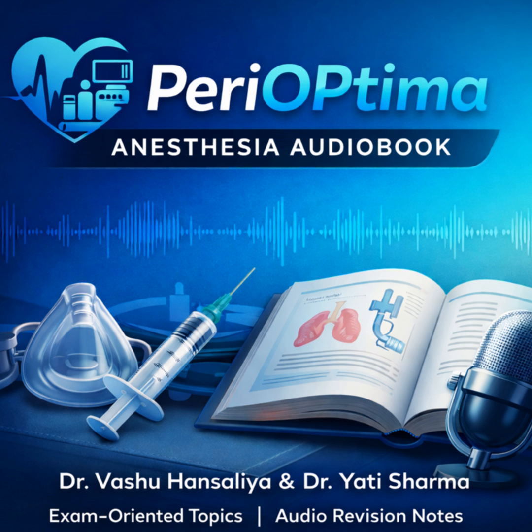Precisely. There's another benefit, too. When steam condenses, it shrinks in volume by a factor of over 1,000. This creates a local suction effect, a partial vacuum, that actively pulls more fresh steam into the pack. That's why steam penetration into wrapped bundles is so incredibly effective. That's a fantastic explanation. It's not just hot air, it's the physics of the phase change.